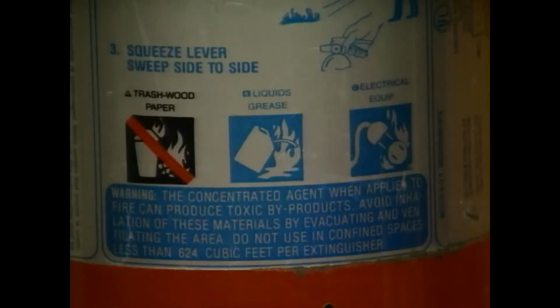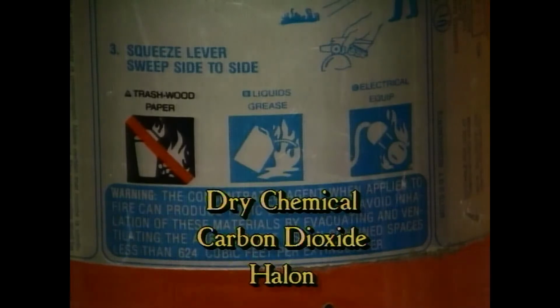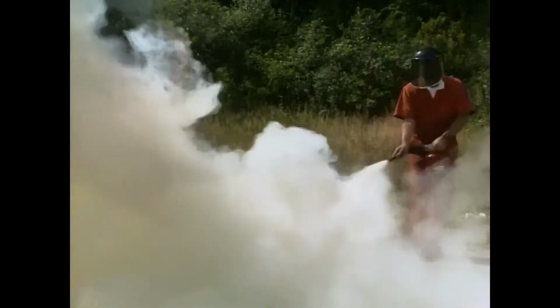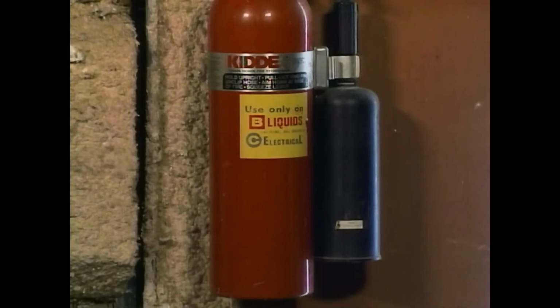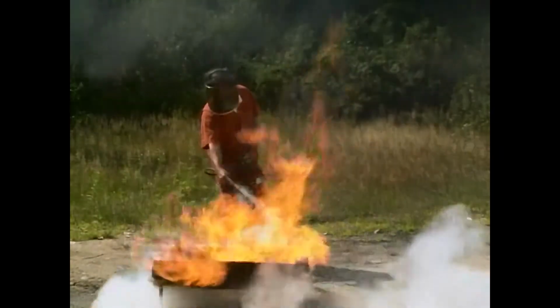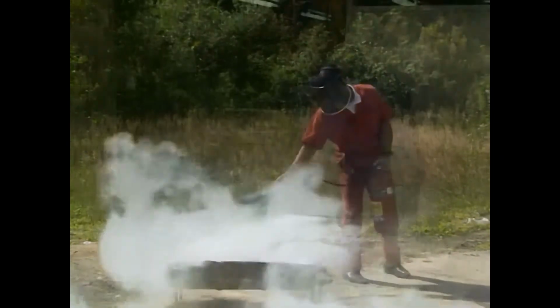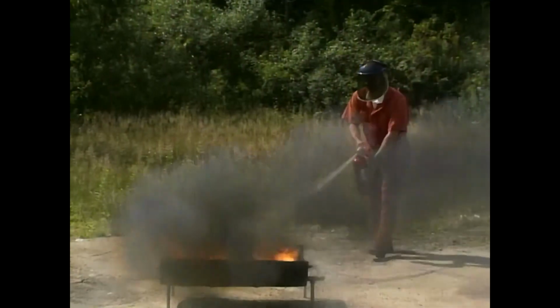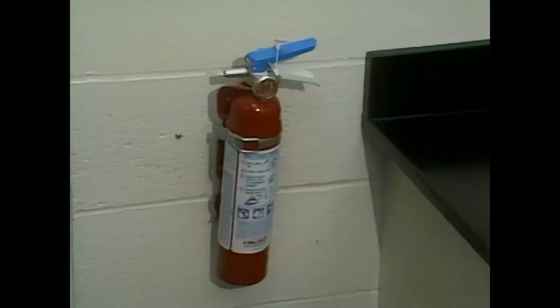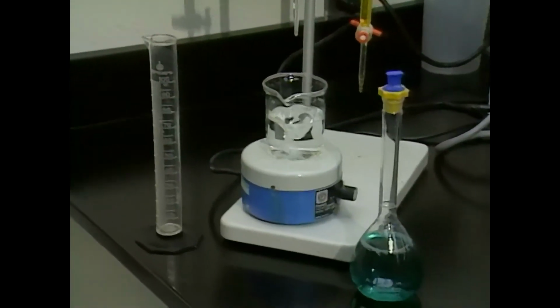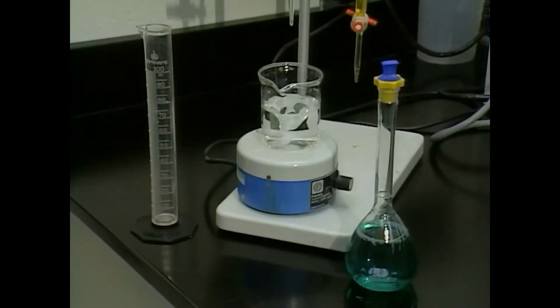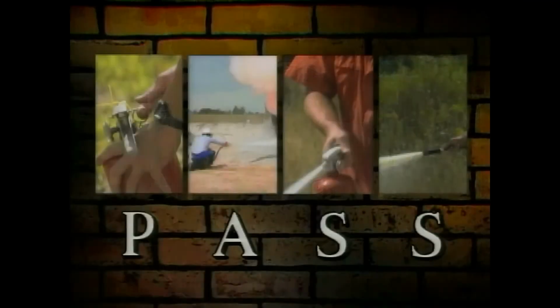Some of the agents found in Class B extinguishers are dry chemical, carbon dioxide, and halon. Dry chemical shoots out a powdery cloud to smother the fire. Carbon dioxide extinguishers eliminate the oxygen in a fire, but care must be taken that dry combustibles do not start up again. Halon extinguishers work by interfering with the chemical chain reaction. Because halon is a clean agent, it is often used in computer rooms or laboratories, leaving no residue on expensive equipment.